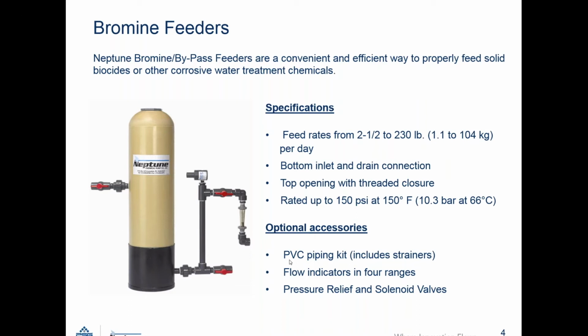We have the optional accessories, which are PVC piping, which you can see here. We also have flow indicators, which indicate how much flow is actually going through the unit. And we have pressure relief valves and solenoid valves available. Relief valves are really required with these vessels because everything is plastic and it's low pressure. You don't want to have any overpressurizing in the system, so relief valves are required.